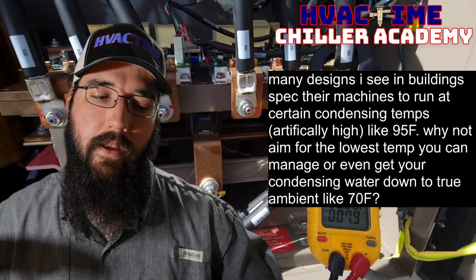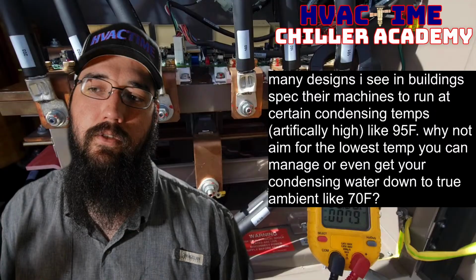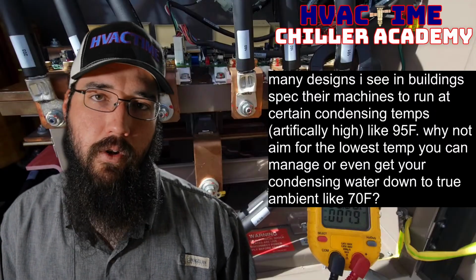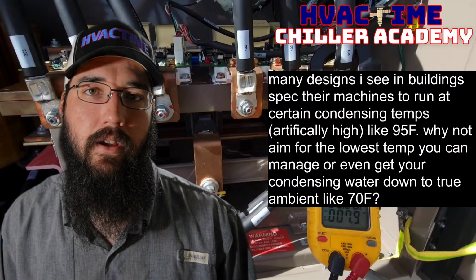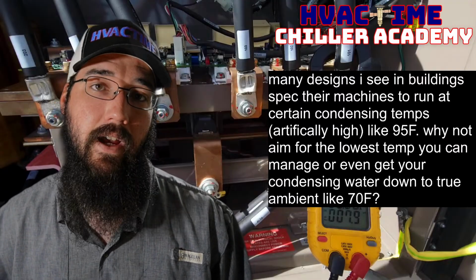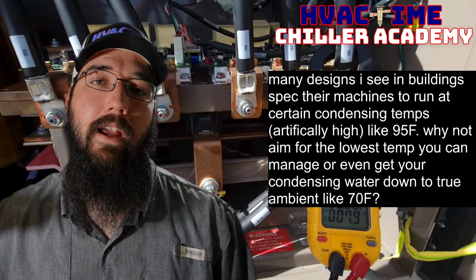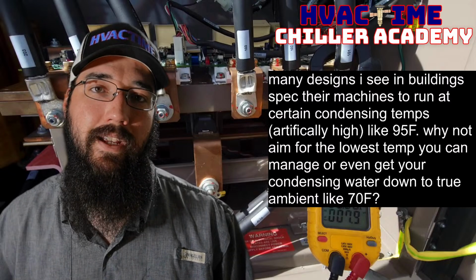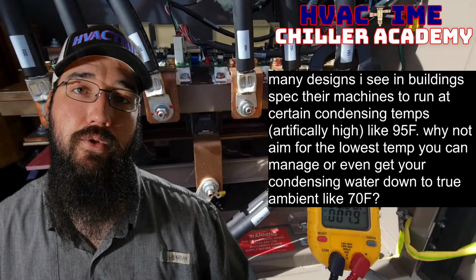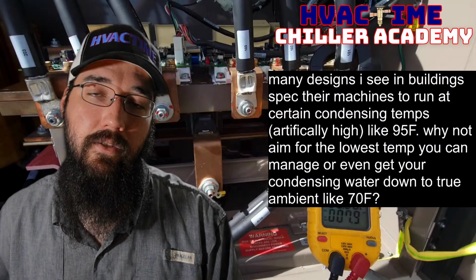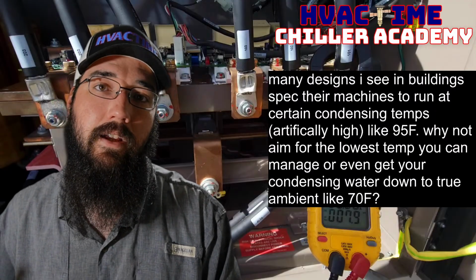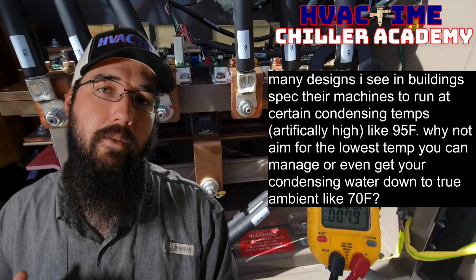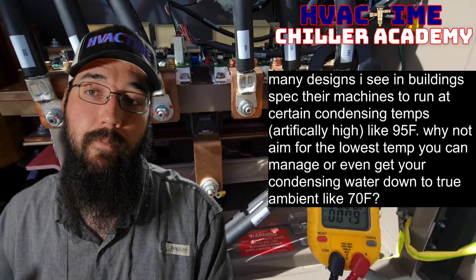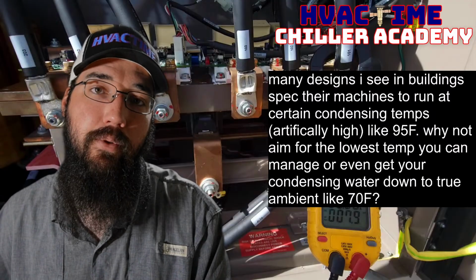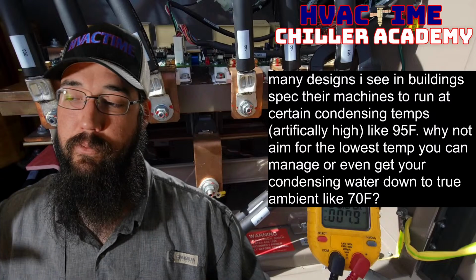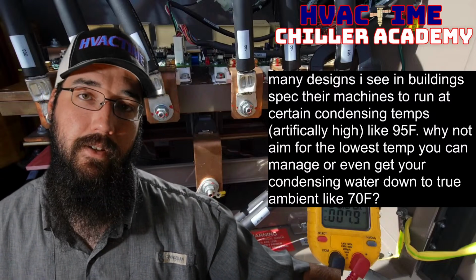And so if we are trying to save energy by slowing down a 50 horse motor in a cooling tower and dropping it by 10 amps, but that means that instead of being able to run a 75 degree condenser water, now we're trying to run an 85 degree and just run that fan a bit slower, those 10 amps are substantially multiplied by a huge factor in the compressor. Because now instead of trying to get that low pressure refrigerant to 75 degrees of saturation, or let's go to a 3-degree approach here, instead of trying to get it to 78 degrees of saturation on the condenser, now we've got to get it to 88 degrees of saturation. That's a pretty big difference. And that requires 10 amps at the tower fan turns into 50, 60 amps at the compressor.